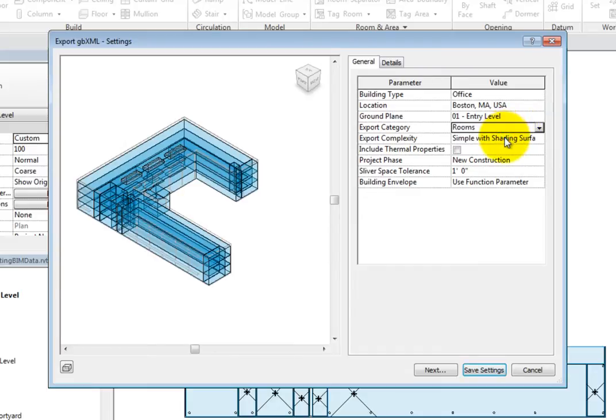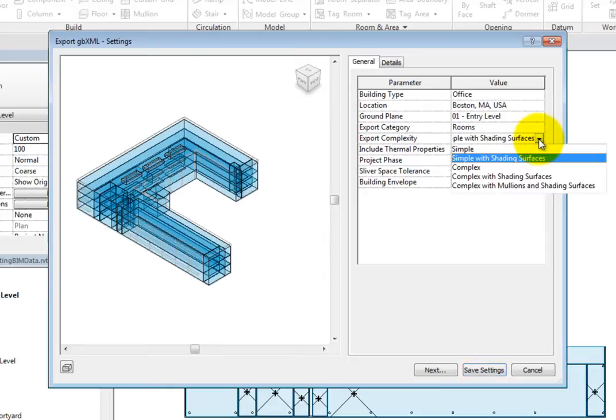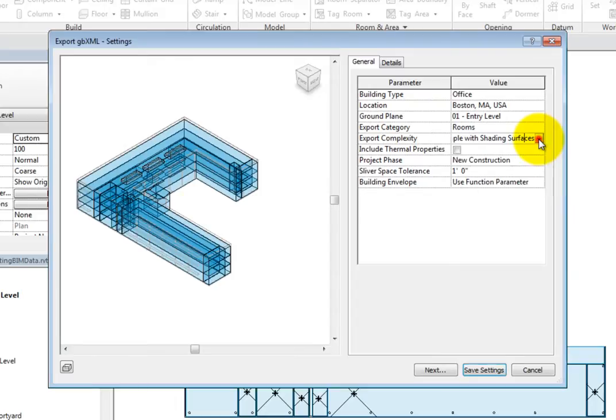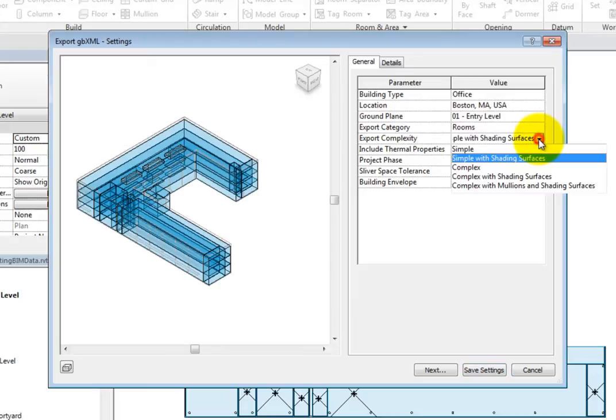For the Export Complexity, you can specify the complexity level of the model. These options range from simple to complex, with and without shading surfaces and mullions. The Export Complexity will determine how much geometry from the building model is exported to the XML file. The simpler the geometry, the faster the analysis results can be obtained.